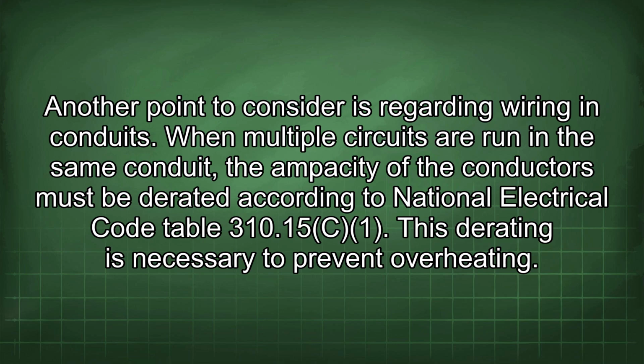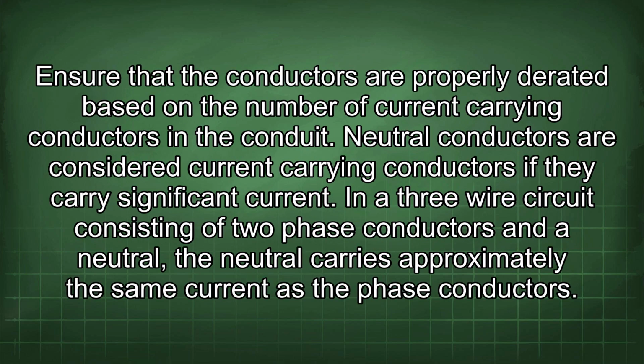When multiple circuits are run in the same conduit, the ampacity of the conductors must be derated according to National Electrical Code Table 310.15. This derating is necessary to prevent overheating. Ensure that the conductors are properly derated based on the number of current-carrying conductors in the conduit. Neutral conductors are considered current-carrying conductors if they carry significant current.